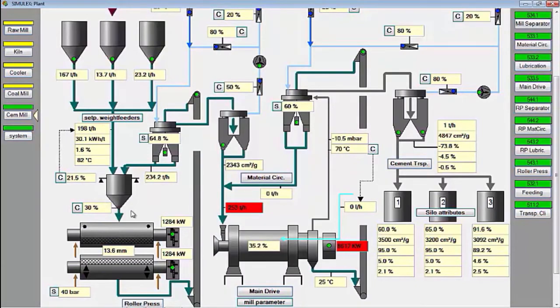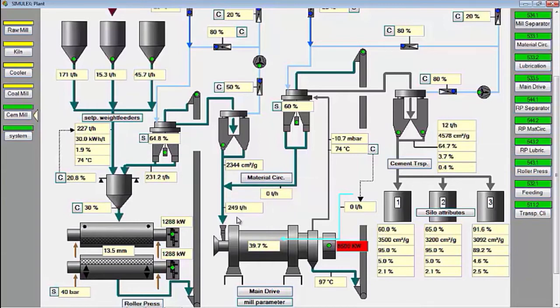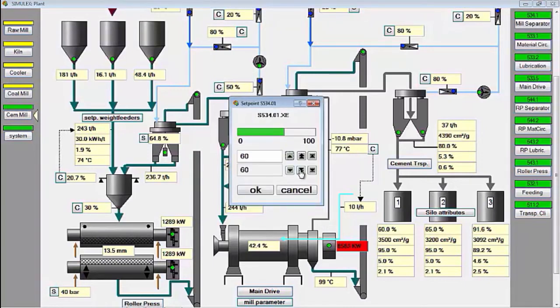Then we observe the material in the mill, tailings material, and the material coming out of the dust collector roller press. The Blaine coming out of the dust collector roller press is maintained between 1800 to 2000 square centimeters per gram. For the smoothness of the product on the roller press, you can adjust the separator speed, the damper opening of the roller press ID fan, the amount of feeding, the hydraulic pressure, or the gap between the rollers. The general roller press gap in normal operation is between 10 and 20 millimeters.